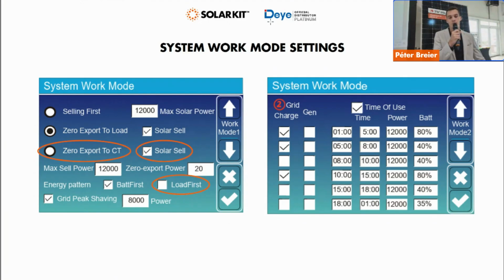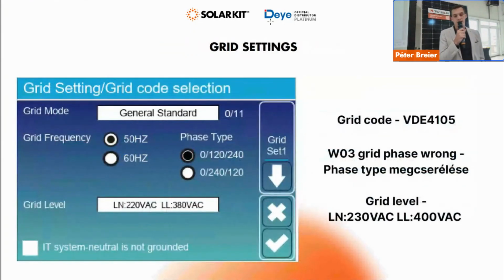So if you raise them, this is basically the same as the battery low percentage on the first few settings that I showed you. But these ones can be set higher. They cannot be set lower, but can be set higher. So if you want a certain time period in which you don't want the battery to discharge, you can raise the percentages there. After that, the grid settings.